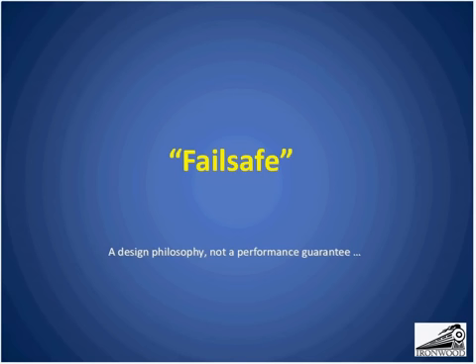Now, that does not, however, indicate that the crossing itself is, quote, safe, unquote, because you run into issues of motorist warning device credibility. If they see warning devices activated for long periods of time with no obvious train approaching, it tends to reduce the credibility of the warning device in the eyes of the motorist. Okay, and that is not a safe thing. So I want to make the point here that fail-safe, quote unquote, is not necessarily safe.